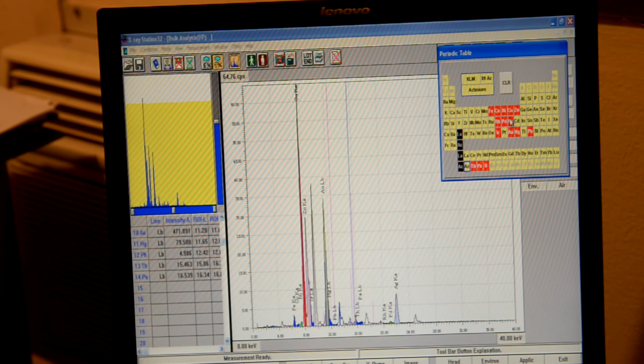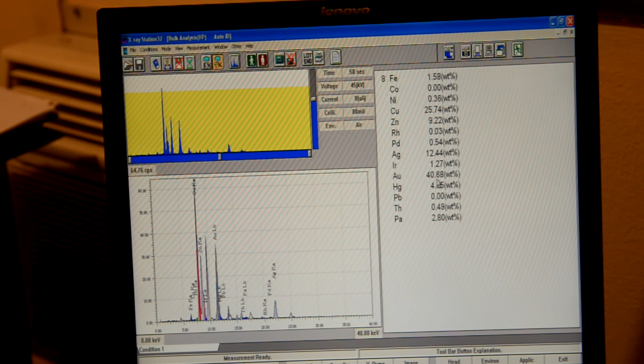So I'm gonna try to find what we have here. This line shows me something present. If we take the traces, which are negligible, we still have Ag, which would be 12.44%, which would stand for the silver. Ag is the silver, and Au is the gold. So when you go for the gold and you put all of those additions, small traces of it, so nickel is 0.36, 1.58% is iron, then you have a silver 12.5%, you have a 40.68 of pure 24 karat gold. So here ends part number 2 of X-ray spectroscopy made easy.